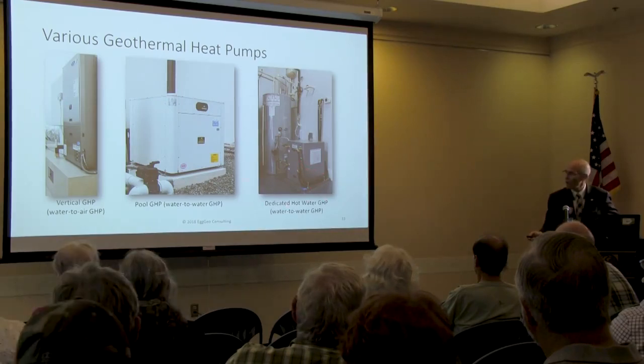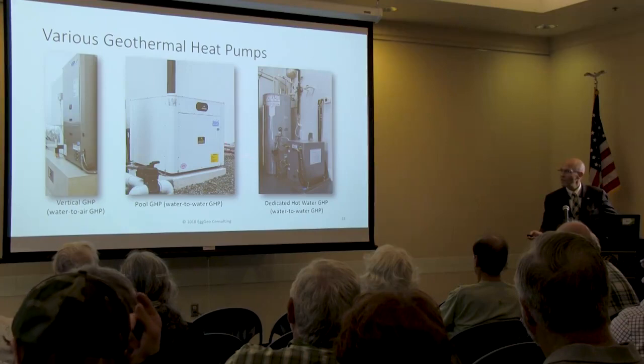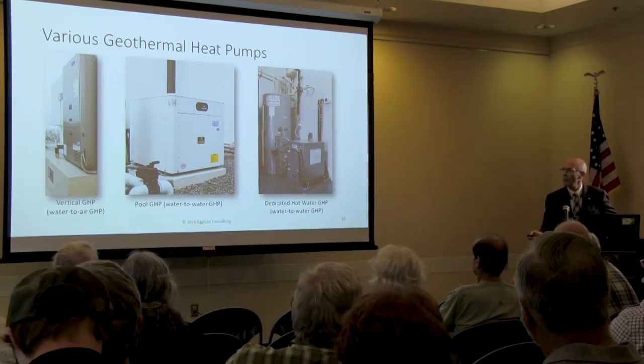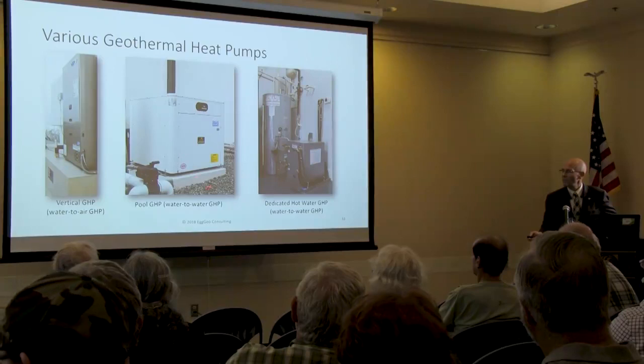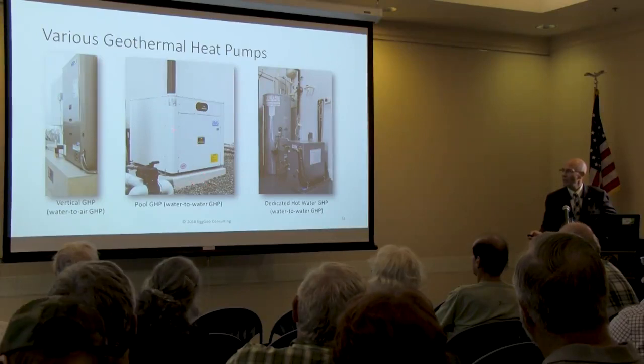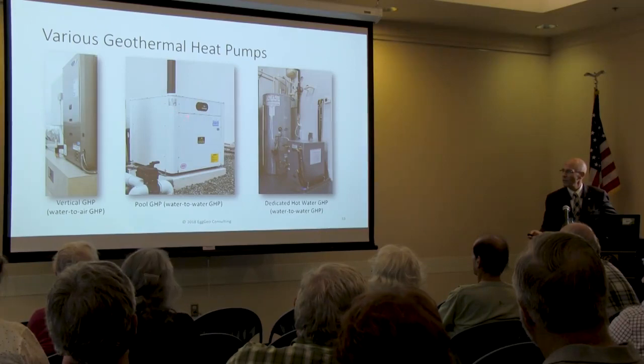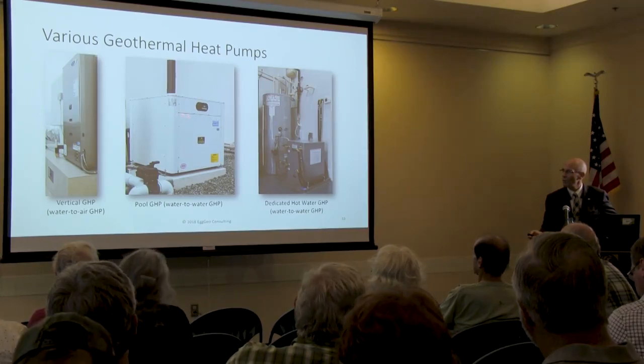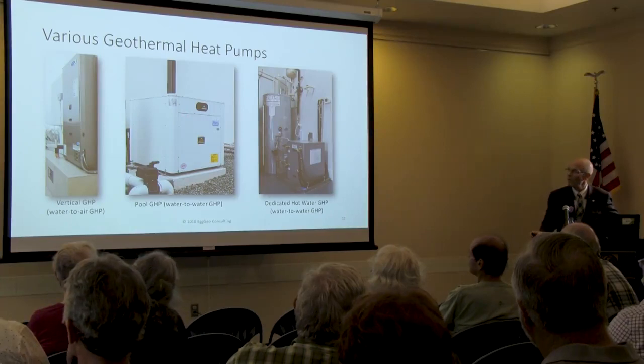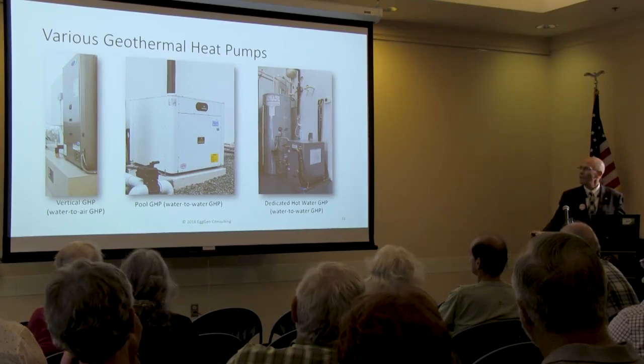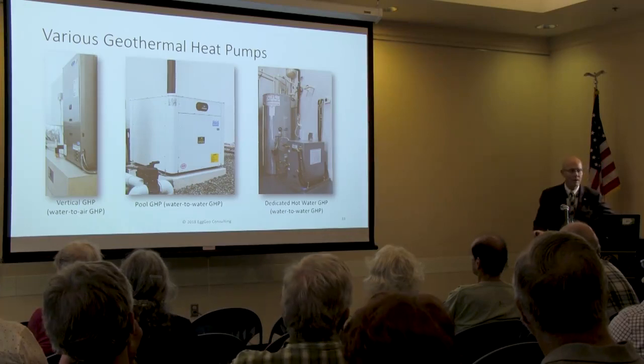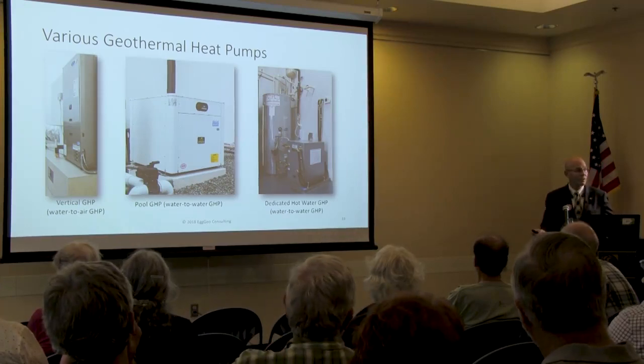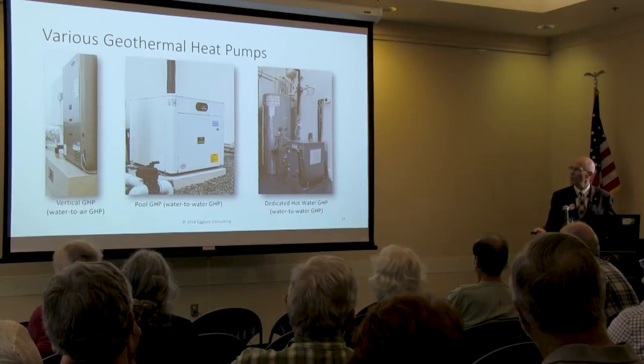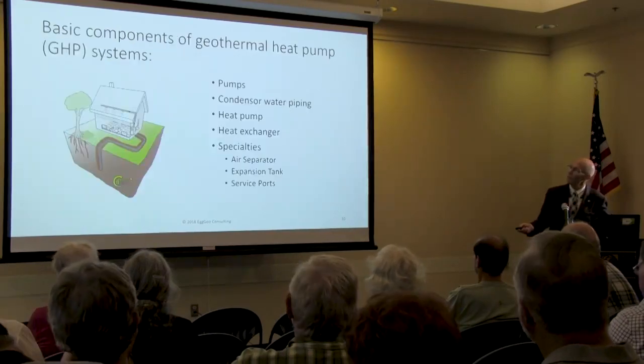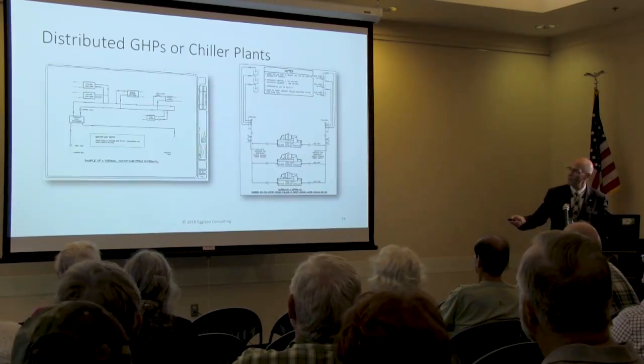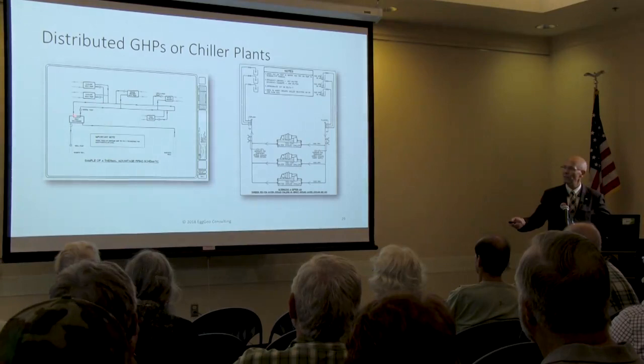Another type of water-to-water heat pump is a pool heat pump. This is a titanium exchanger pool heat pump, and it exchanges water from a ground loop through a titanium exchanger and using a standard Carnot refrigeration cycle to the pool water, the chlorine water in a pool. So in a given home, aquatic center, Marriott hotel, or anything, you'll probably see these three different types of heat pumps. They're all geothermal source, and the one thing that is common to all of them, here it is right here, is they can all be tied to a common condenser water loop.